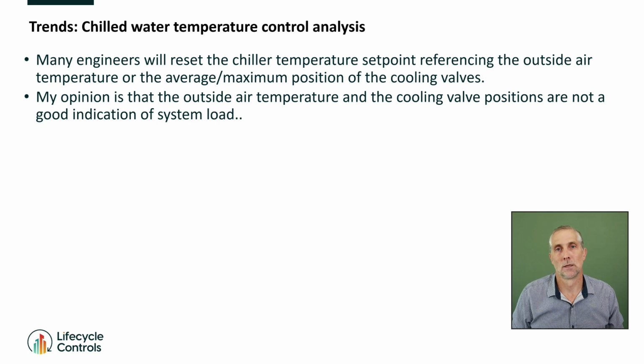You can't do that. In the old days with the fixed pressure set point, 250 kPa fixed, the cooling valves were an indication of the load and you could use them to reset the chill water temperature set point. But we always reset the chill water system pressure set point. We always do that. So we can't use the cooling valve. So there are hundreds and hundreds of buildings in Australia where the chill water temperature reset strategy completely doesn't work. And it's likely there are thousands and thousands of buildings in the world where we're resetting like this, and it's not working.